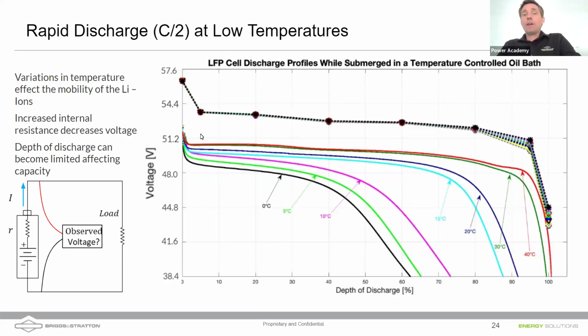Those elevations or decreases in the overall voltage also depend on the temperature of the battery. A cold battery discharging, depending on how cold it is, influences the viscosity of the electrolyte, and you'll get an overall increased internal resistance at lower and lower temperatures. So if you're discharging in really cold conditions at a very fast rate, you might see your batteries dip below 48 volts, even at 50% state of charge.